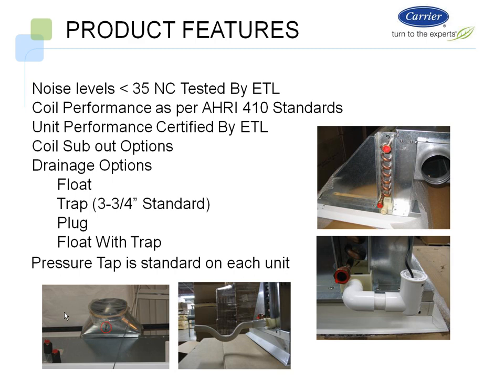Now, if they don't plug that hole, with chilled beams in an active start, it becomes very, very critical. Let's say you're losing 10 CFM. If you lose 10 CFM out of that little hole, you're actually losing 40 CFM at the beam inside the space. So it becomes a bigger concern. That's why there's a tap on every unit with a cap on it. They take the cap off, make their reading, hopefully put the cap back on, and you're fine.